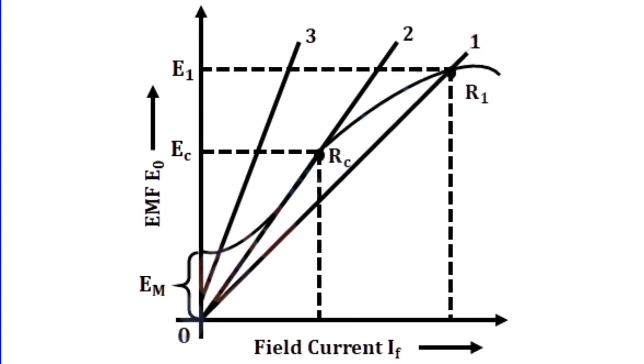Critical field resistance represents a pivotal threshold in the operation of a DC shunt generator. It is defined as the maximum field resistance value that still allows the generator to build up voltage when operating at its rated speed. In simpler words, if the resistance in the shunt field circuit exceeds this critical value, the generator will fail to generate the required voltage. To understand why this happens, we need to consider the relationship between field current, magnetic field strength and induced voltage.